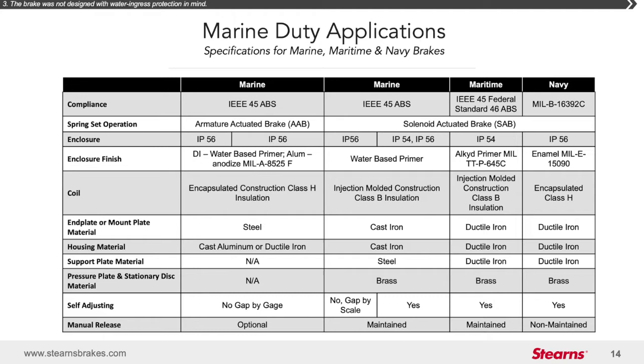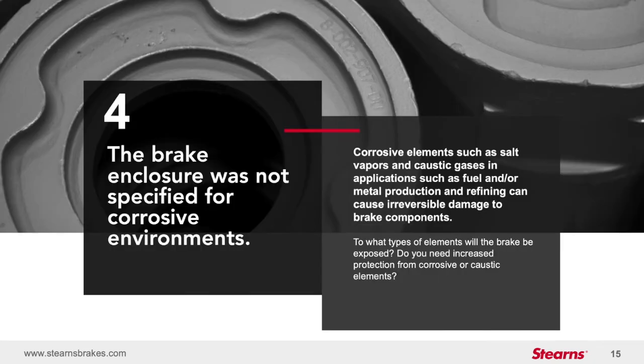It's important to note that it is a best practice to talk to your brake manufacturer to ensure you're purchasing a properly rated brake along with modifications appropriate for the specific application. The fourth avoidable mistake is the brake enclosure was not specified for corrosive environments. The climate of a region can have a large impact on corrosive characteristics. Coastal areas affected by airborne salts and cold regions where de-icing is a regular occurrence are examples of environments where special attention must be given to enclosure selection.